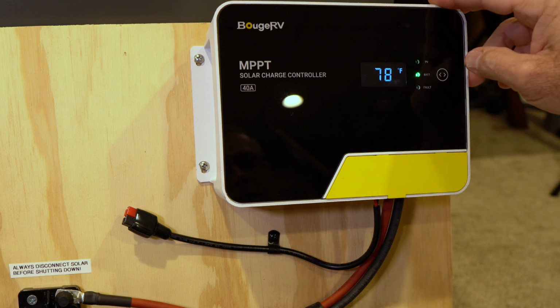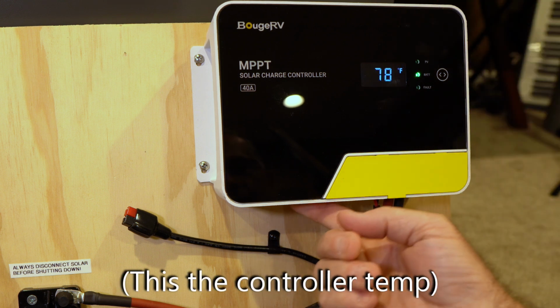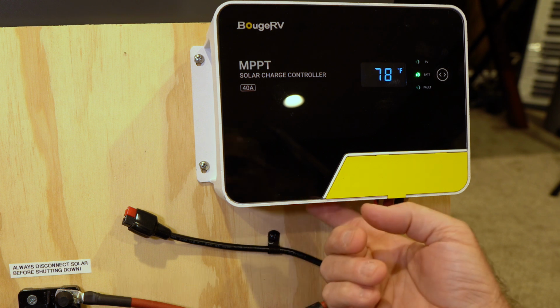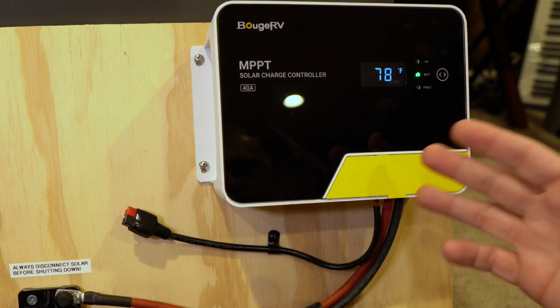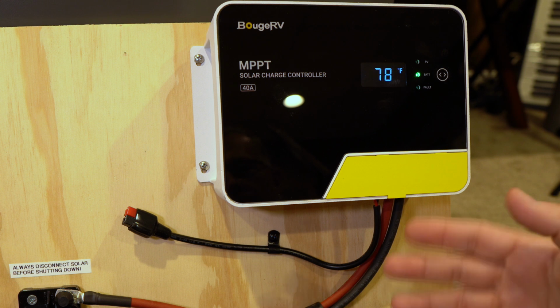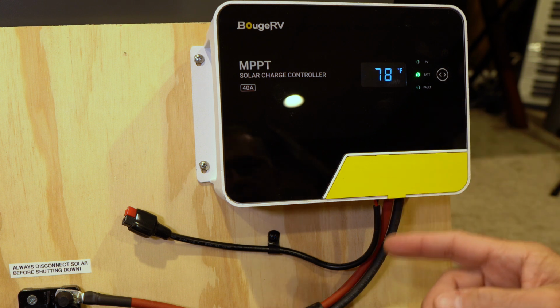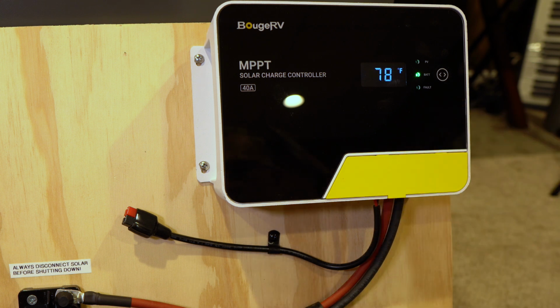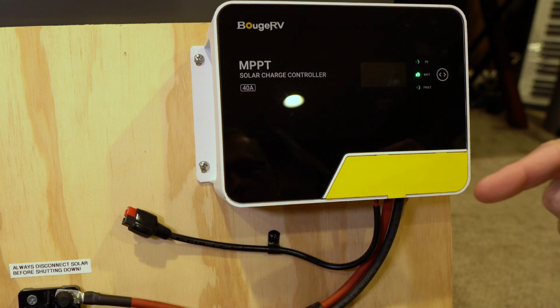Currently showing 78 degrees Fahrenheit. I don't have the battery temperature probe plugged in, since that's primarily for temperature compensation, which is essential for flooded lead acid batteries. It doesn't do much in this case for lithium ion, which I'll talk about more in my closing comments.